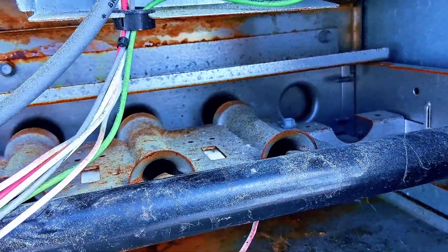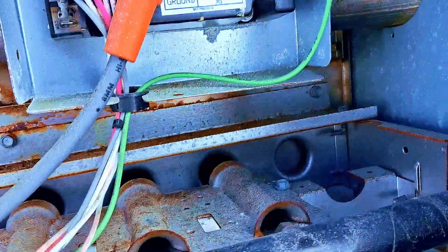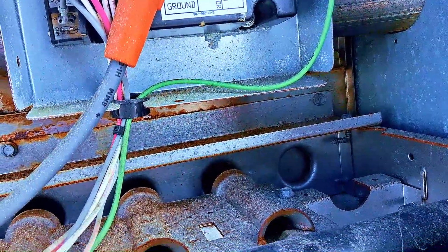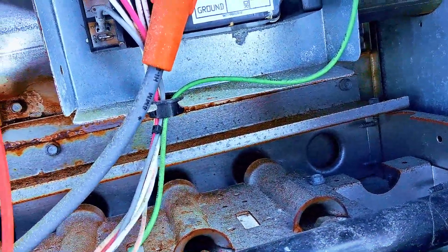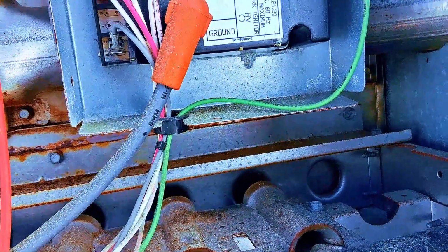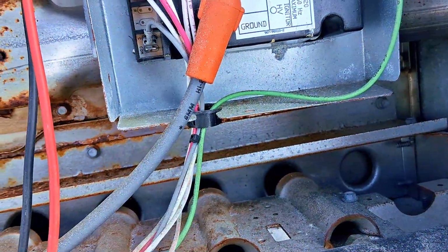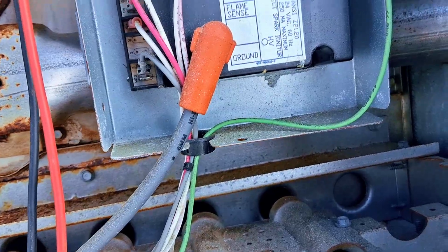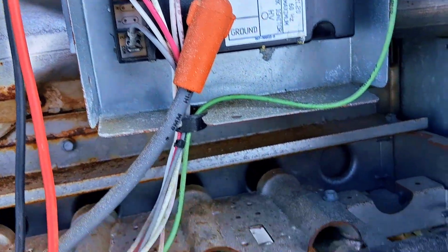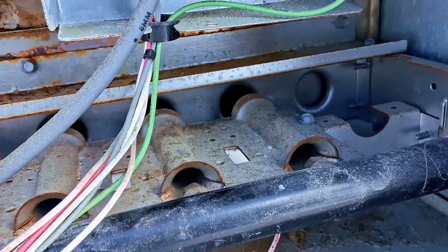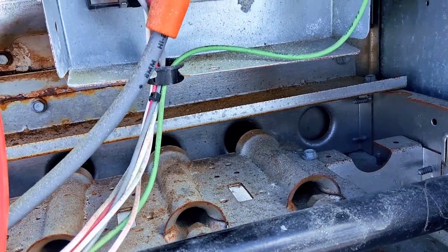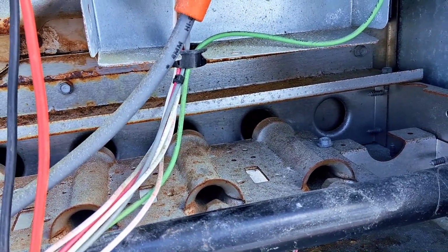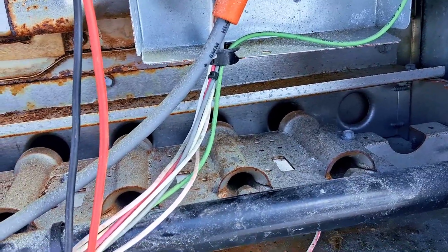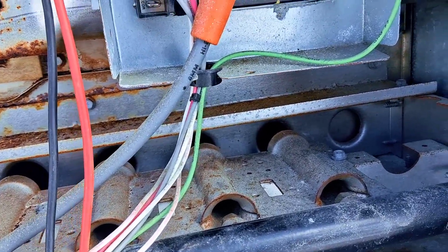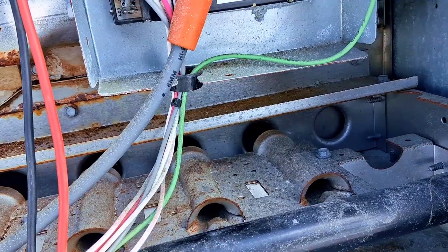So now I gotta check the amps coming off that thing, and also I need to check my ground on this, because if it's not grounded properly, it's not gonna send a good signal back properly. So I gotta check one of those two things. I'm gonna get my other meter that reads microamps, with some clamps where I can put across it, and see if I got low microamps coming back to the board.